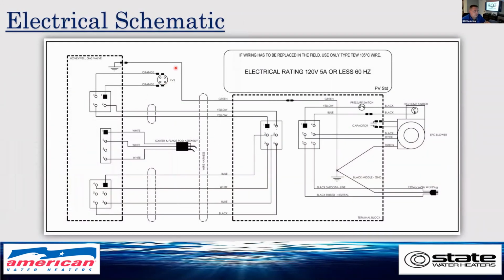This is a very important procedure to know in order to troubleshoot. The electrical schematic is a sticker that's on the heater, and it's very handy to know what wires do what. So when you need to test a pressure switch, knowing one of the wires is coming off the black, coming off the high limit switch, and the other one would be the yellow. Your power going up to your blower would be number 2 and 5 coming off of that, which are black and white. Your ground obviously being green. It's a very handy tool in the aspects of troubleshooting.